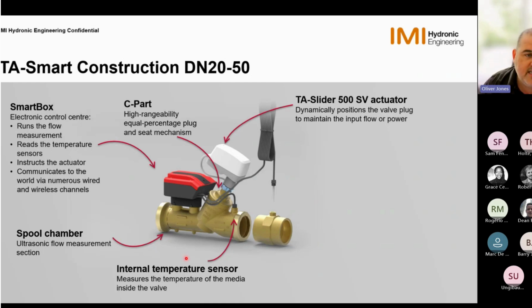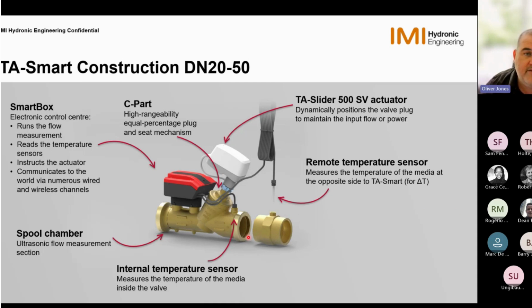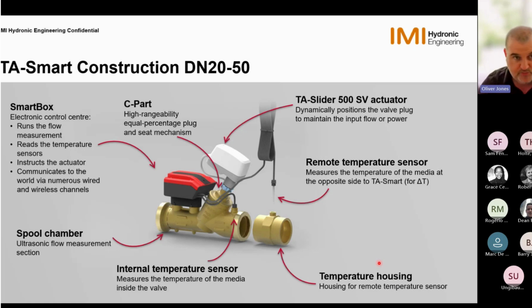We also have our internal temperature sensor. So this is what's measuring the temperature of the media inside the valve. And then we have our remote temperature sensor, which is placed on the opposite side of the TA Smart. And this is what's giving us our delta T and also is what's helping to calculate our power. And then with the smaller ones, with our 20 to 50 mil DNs, we actually get a temperature housing in the box. So this is a housing for the temperature sensor to be sat on the opposite side of the position of the valve. So if the smart's on the flow, the housing goes on the return, or vice versa. And we can tell the valve through the app which side it's actually sitting on.